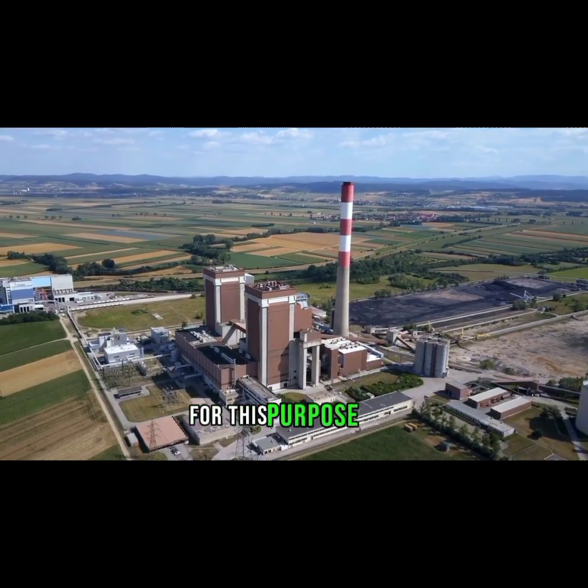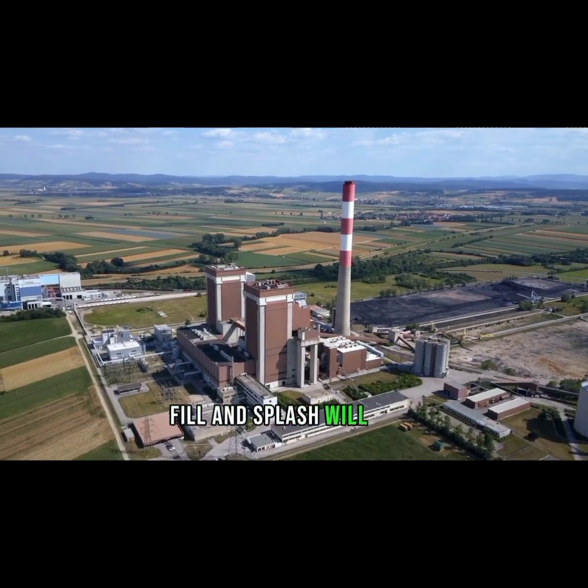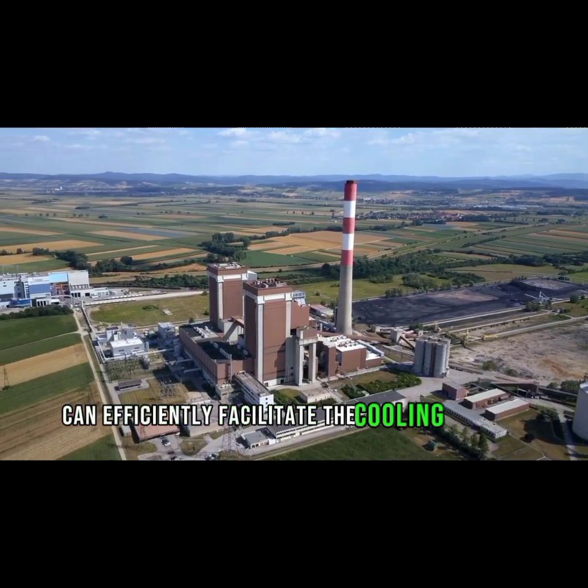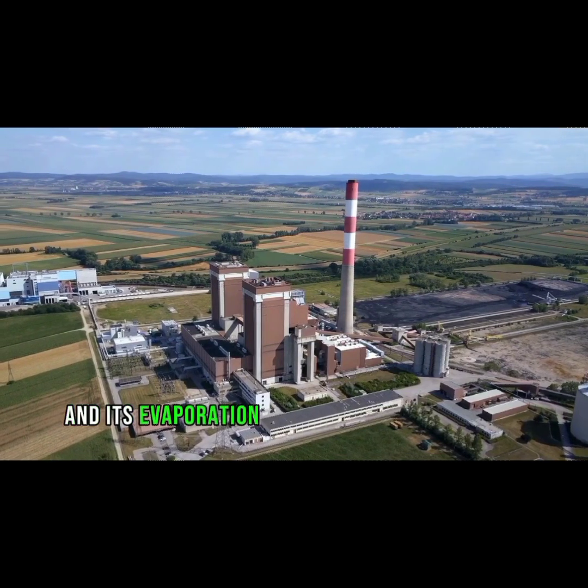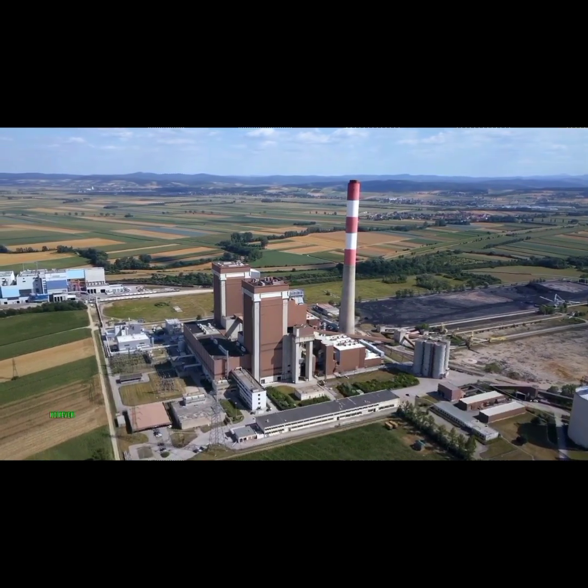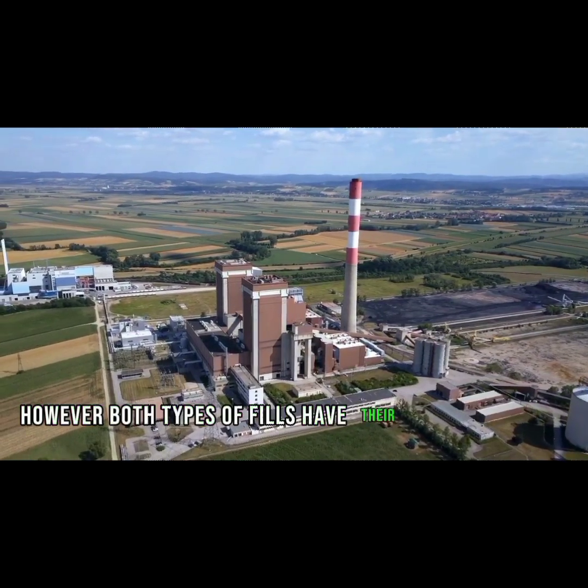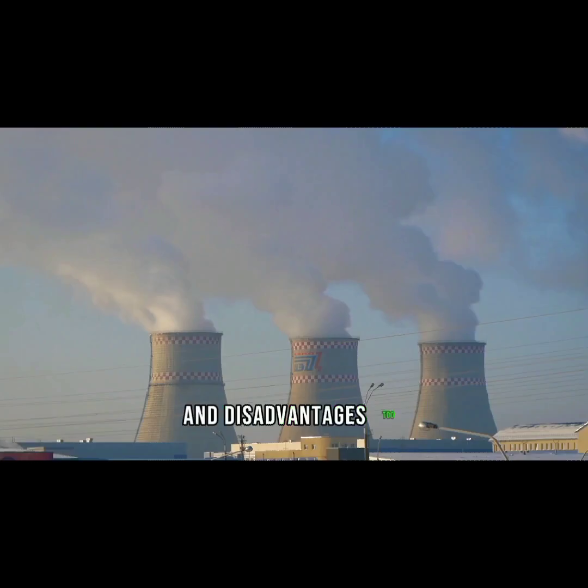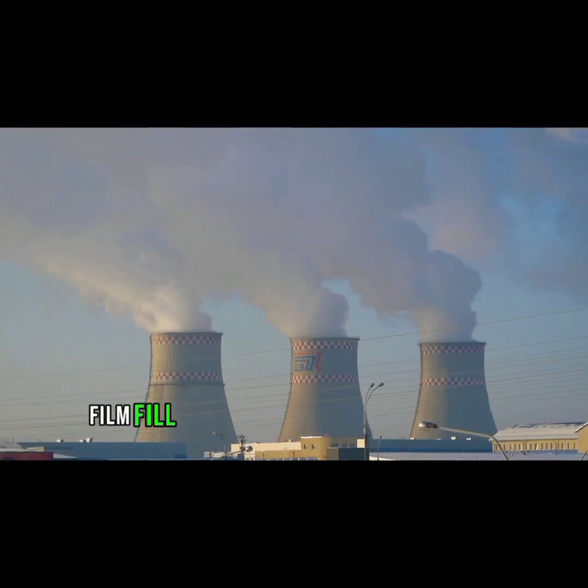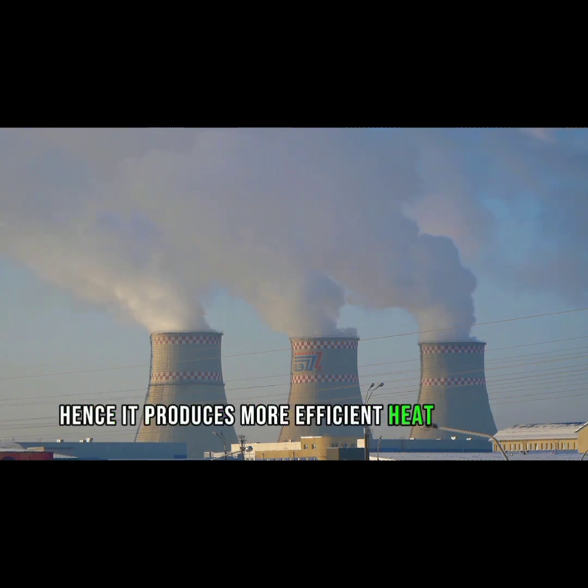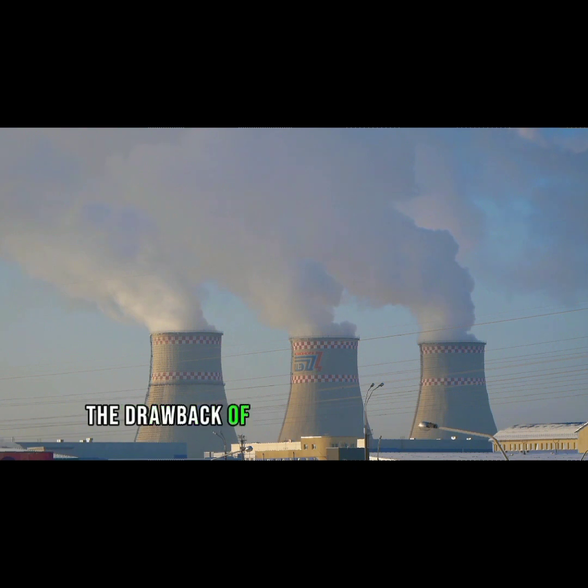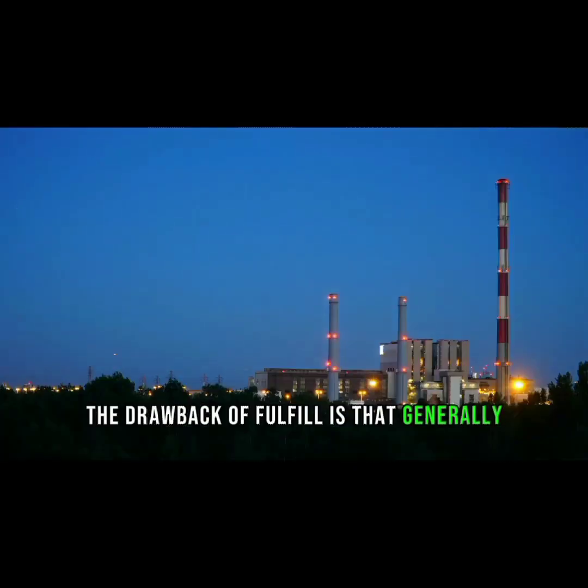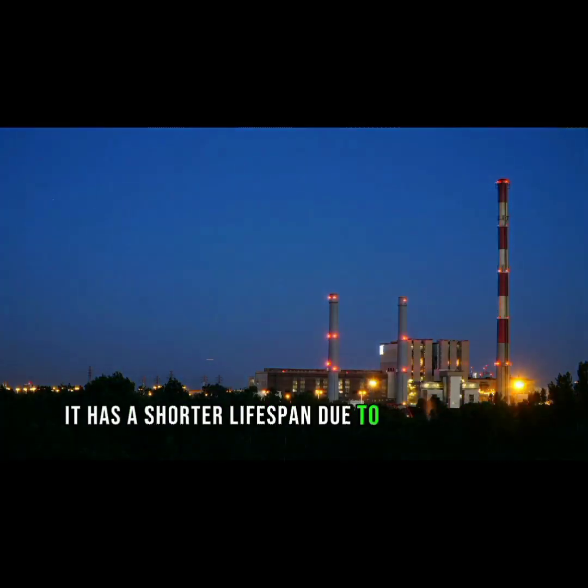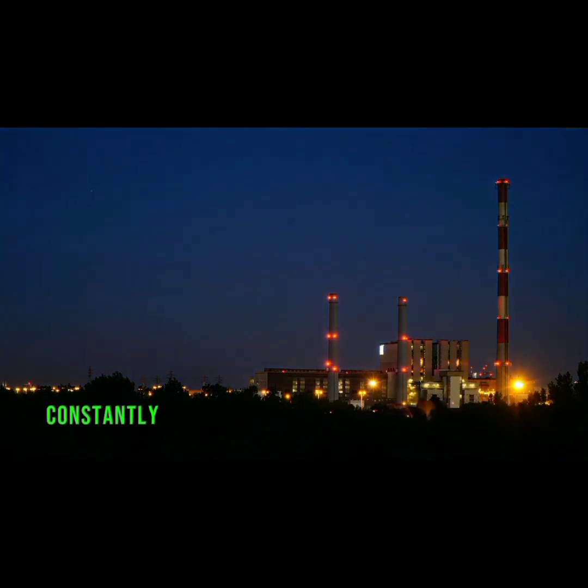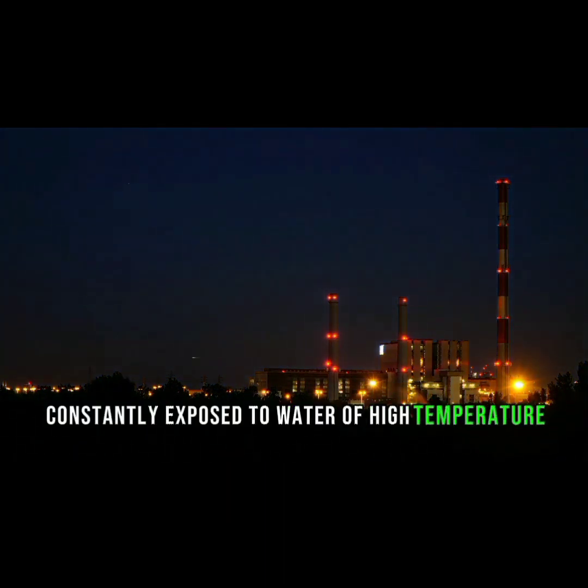For this purpose, film fill and splash fill both can efficiently facilitate the cooling of water and its evaporation within the cooling towers. However, both types of fills have their own advantages and disadvantages. Film fill generates a bigger surface area, hence it produces more efficient heat transfer. The drawback of film fill is that generally it has a shorter lifespan due to more wear and tear, as it is constantly exposed to water of high temperature.